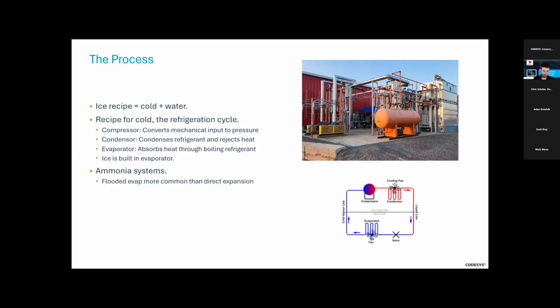We generally work with ammonia systems, as that's common for these large scale ice plants, and they run a bit differently for those familiar with automotive and home air conditioning - we run flooded evaporators instead of direct expansion. So we have the whole evaporator full of liquid ammonia, either through a surge tank system or a recirculating system, and that ensures good direct contact with those plates for a little more efficiency.